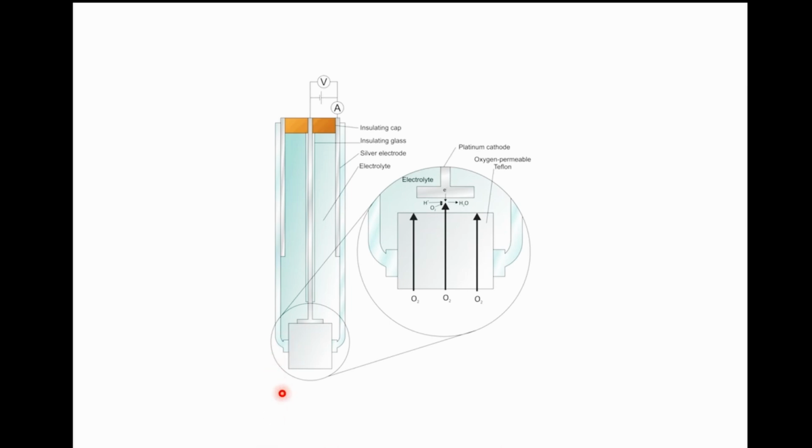And so this thing can be manufactured real small, and they can shove it up your vein. And there's an electrochemical cell that has a silver wire and some silver solution. And then this other electrode is based on oxygen concentration. And here's a semi-permeable membrane. The oxygen gas in your blood can diffuse through there. Here's this platinum cathode. This reaction happens, develops an electrical potential.